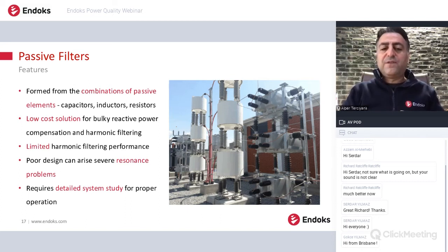So passive harmonic filters require more detailed system study for proper operation. It is very important. You have to study the system, you have to study the load, and you have to calculate the parameters of the filters, and you should take some measures if there is a risk of resonance in the system, and you should put the correct design and the right thing on the system.